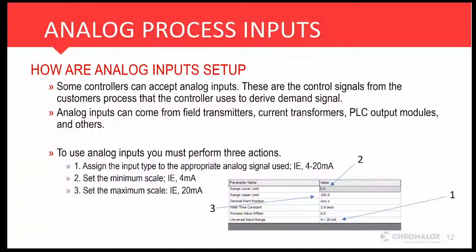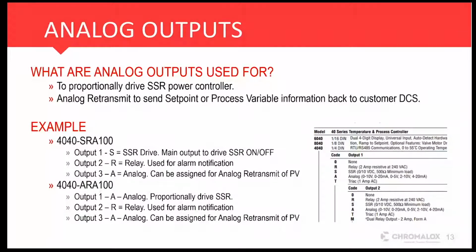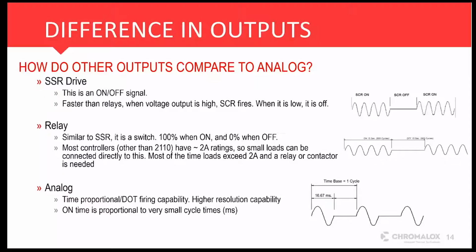And that's what we touch on in those videos, and we walk you through inputs, we talk about scaling, how to integrate with the PLC is certainly part of that. And then obviously selection, we're going to go through in a minute with Vince. But your controller specific, that's actually the first thing I generally ask when somebody calls in. What is the controller? And it's not, is it a 4040? It's a 4040 what? So now we understand how many inputs we have, how many outputs we have, and how we can now understand why is it not behaving as the customer anticipated.